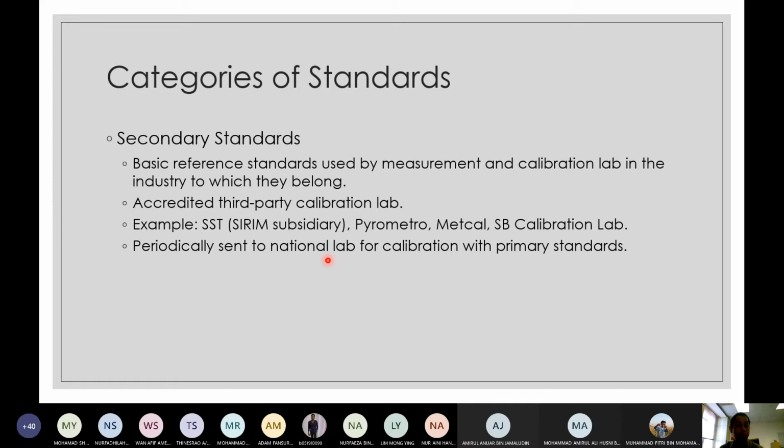Next, we have secondary standards. These are the basic reference standards used by measurement and calibration labs in the industry to which they belong. For example, in the manufacturing industry, they have some reference equipment, and they are going to refer to secondary standards. Secondary standards also refer to accredited third-party calibration labs. For example, we have SST, which is a SIRIM subsidiary. These labs control the secondary standards, and periodically send them to the national lab for calibration with primary standards.